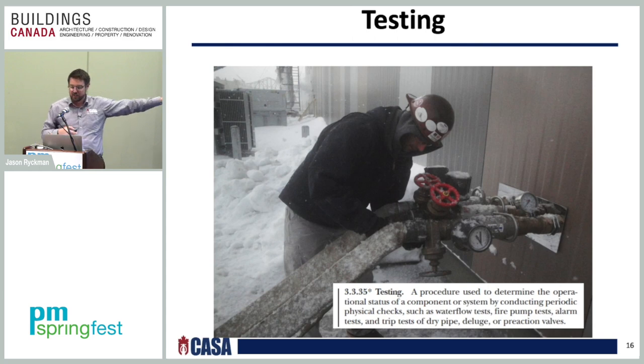Testing. This poor guy, in the middle of winter. It's a fine example of how, when you're doing your tests, you have to make sure you do them in the warmer months, especially being here in Canada. We had a nasty winter this year. This gentleman is doing what we call a fire pump test. He has some flow meters on the test header, and basically he's doing his test. Again, a fine example of doing your testing in the summer months.